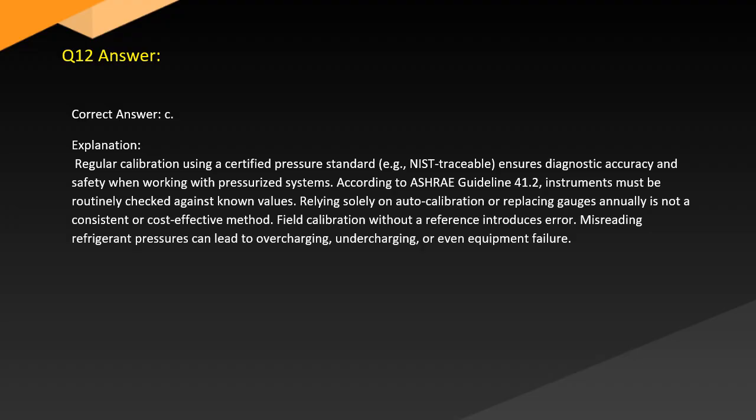Answer. Correct answer: C. Explanation: Regular calibration using a certified pressure standard, e.g., NIST-traceable, ensures diagnostic accuracy and safety when working with pressurized systems. According to ASHRAE Guideline 41.2, instruments must be routinely checked against known values.